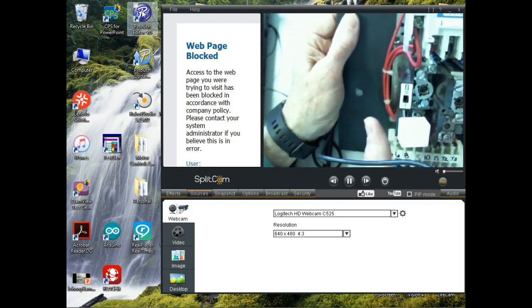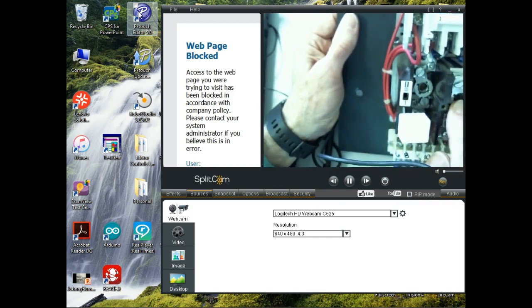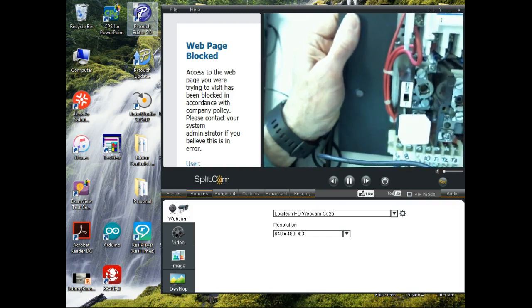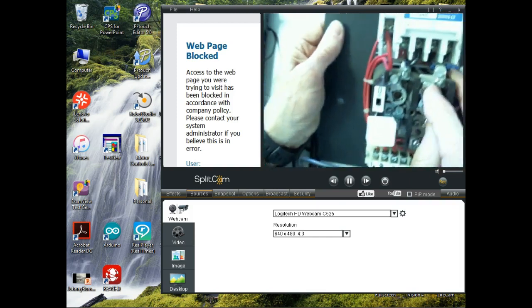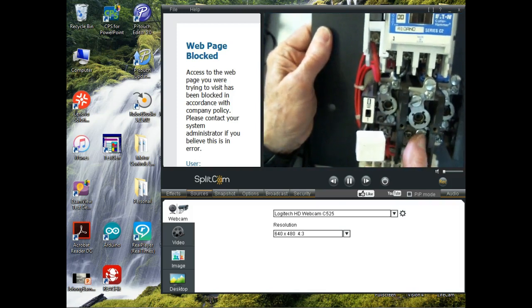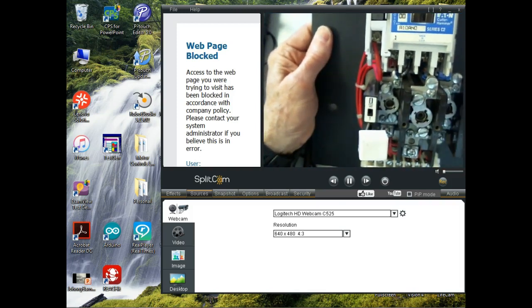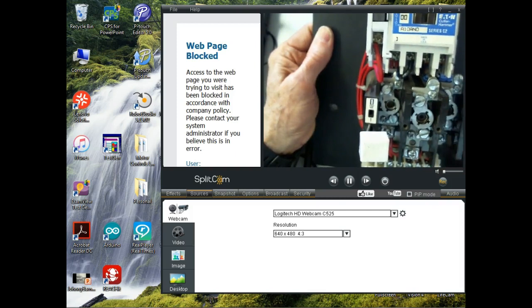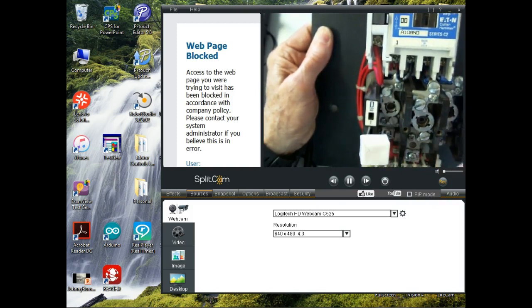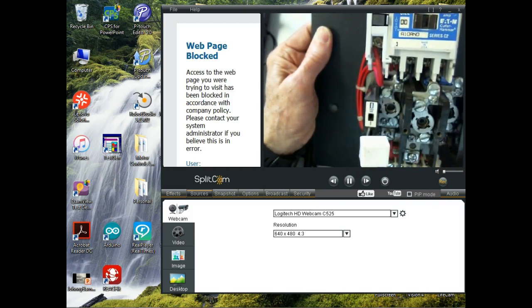The problem is if I put a different motor on this thing that's wired for a different voltage, then I'm going to have to change the heaters out, right? You understand? The heaters are not hard to replace. We just break this screw out here, this screw right here. We pull the thing out, find the right heater, and put it back in there. And you have to put the same heater in all three phases on a three phase. On a high voltage two phase, it usually has two heaters. You need to put the same heater in both lines, right? You understand? All that makes sense.